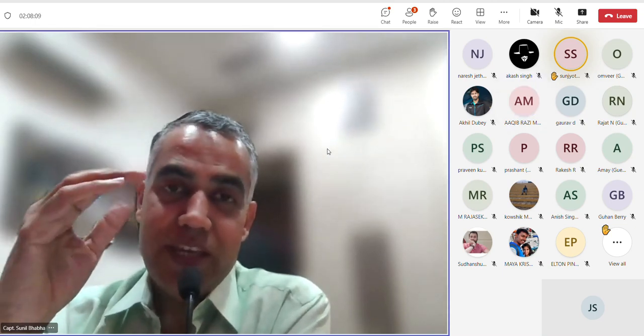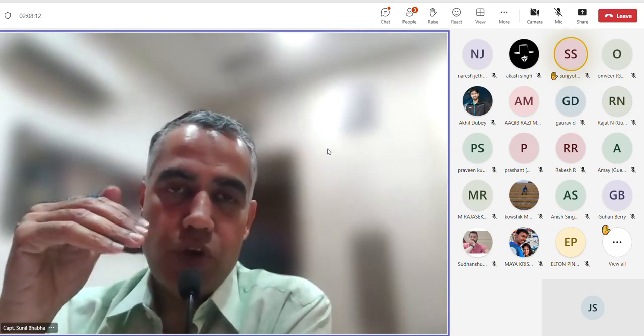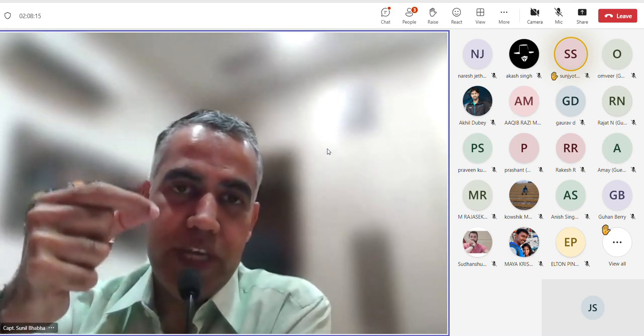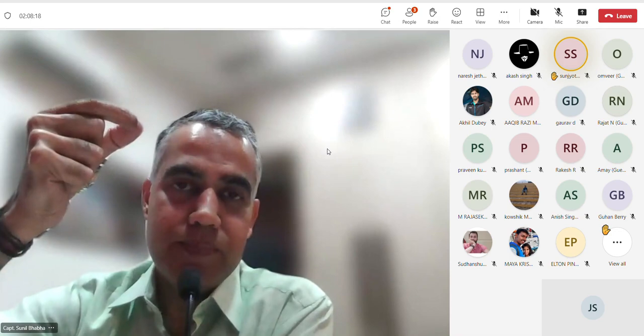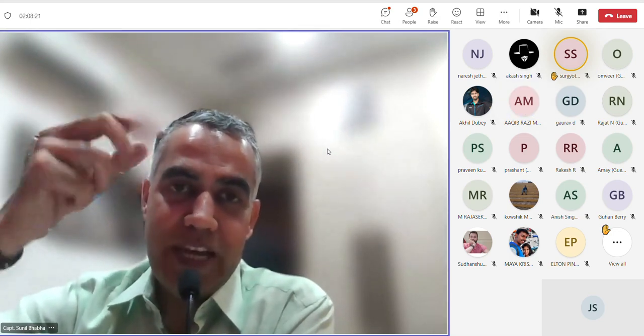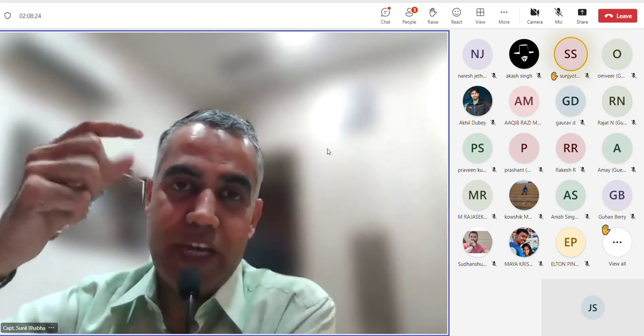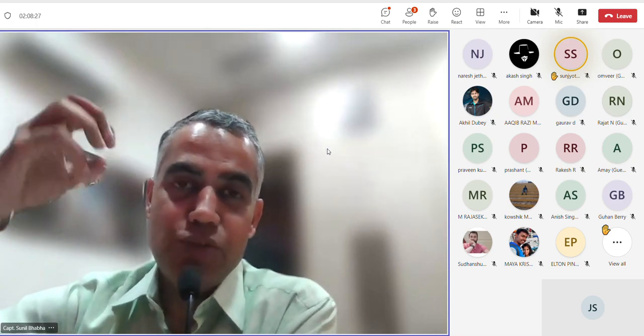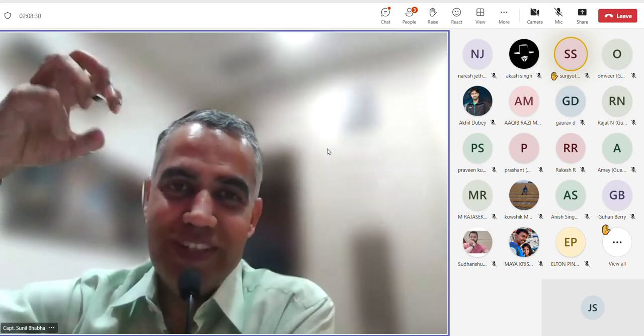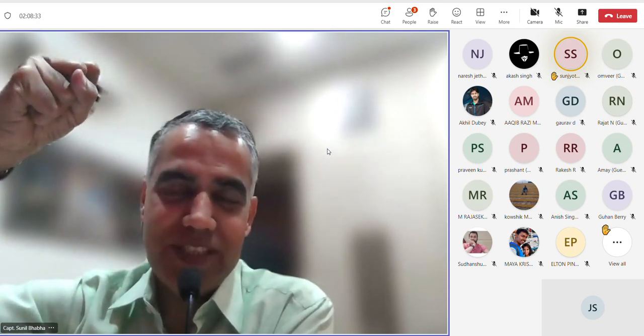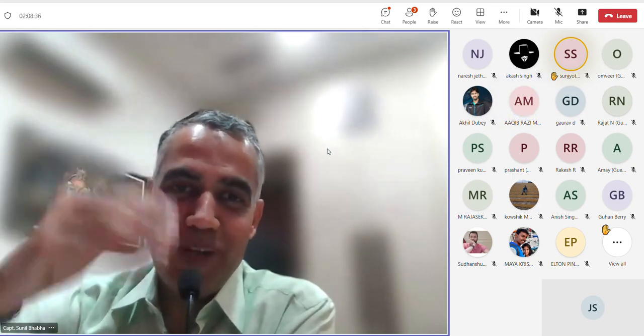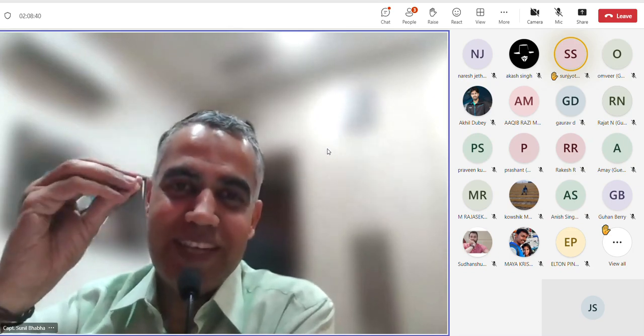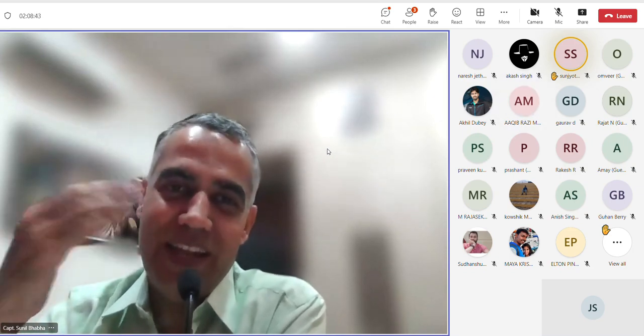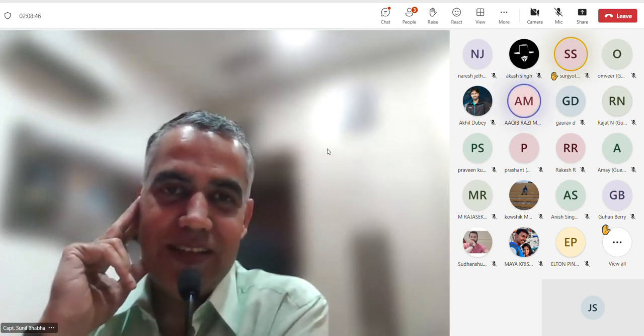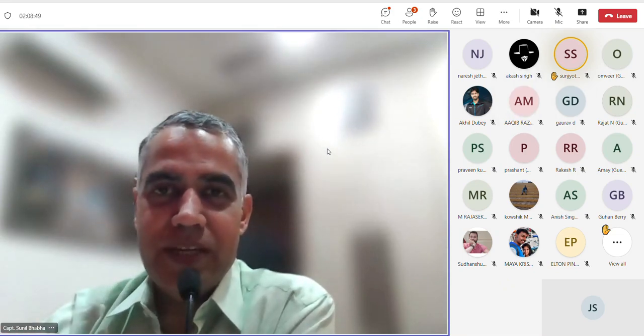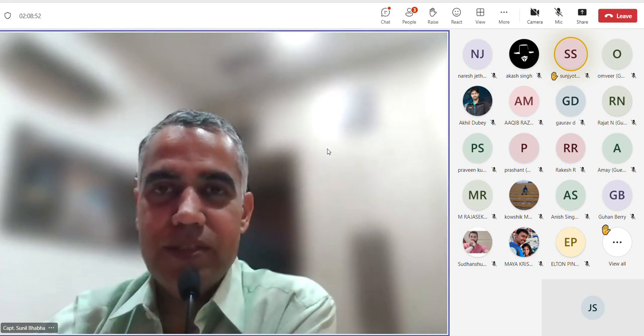It works for shallow waters, but when you go in deeper waters, the echo is going to take a longer time to go back and come. Till the time the echo comes back, the transducer cannot start the next transmission, because if it starts the next transmission, it will not be able to catch that pulse. So it needs to wait for that pulse to come back, and for that, the pulse repetition frequency has to be slowed down. Lesser number of pulses in a second. Clear, sir. Great, beta. So let's go back to the presentation.